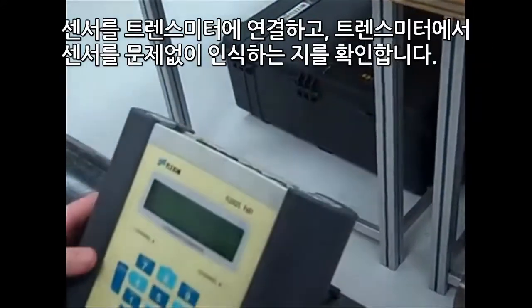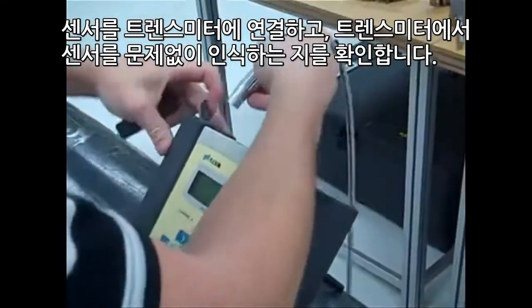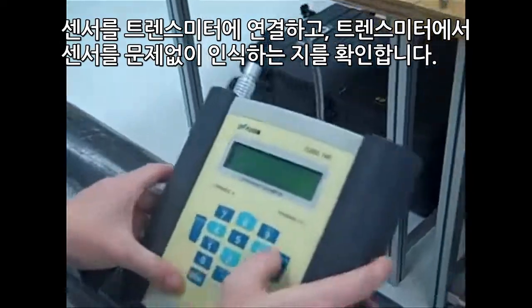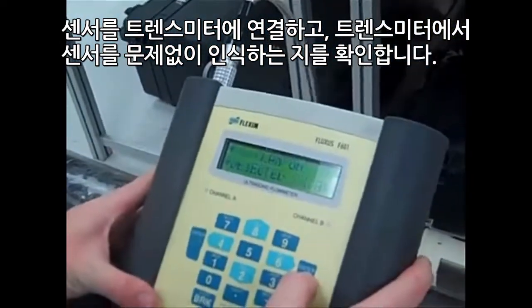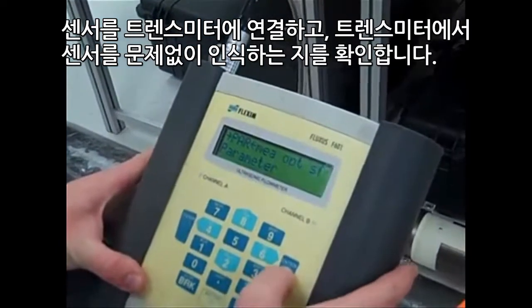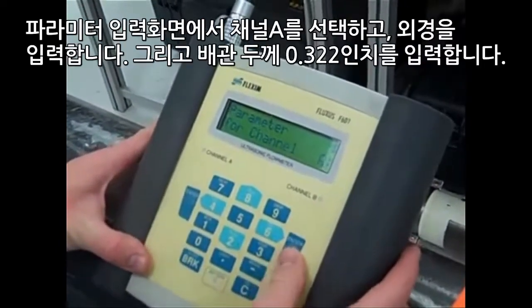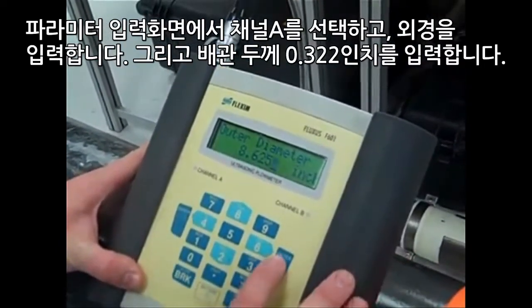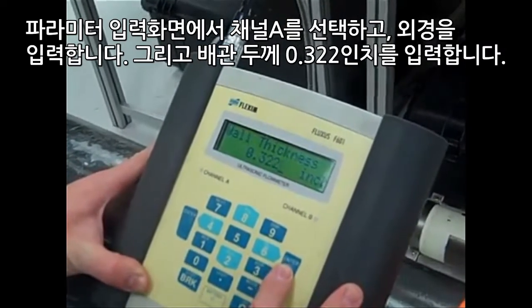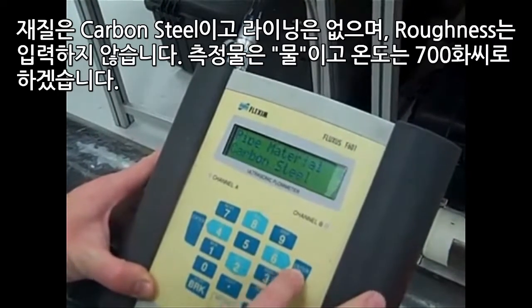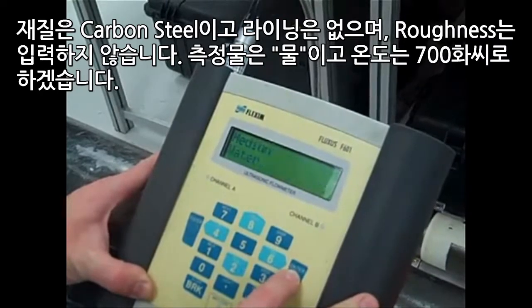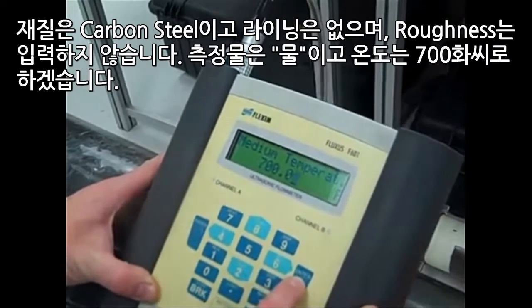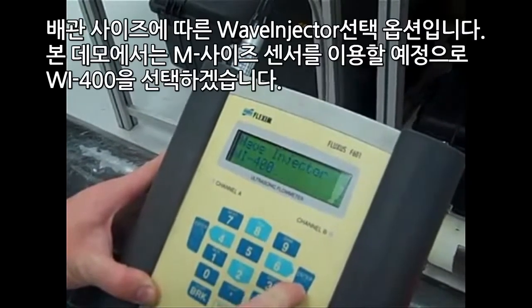First you want to plug in your transducers. Make sure that the flow meter reads the transducers. Go into parameters for channel A. Enter in your outer diameter and your wall thickness, 0.322 inches. Carbon steel pipe, no lining, roughness, water, and let's say we're working at 700 degrees Fahrenheit.